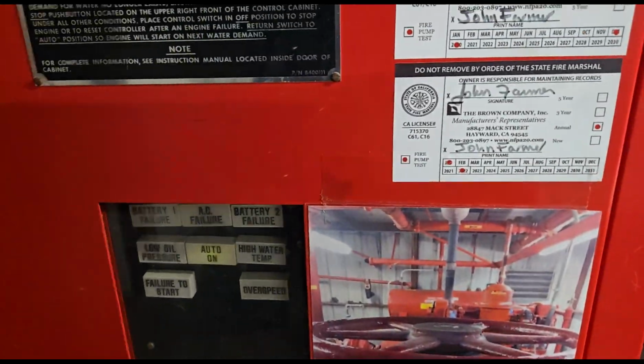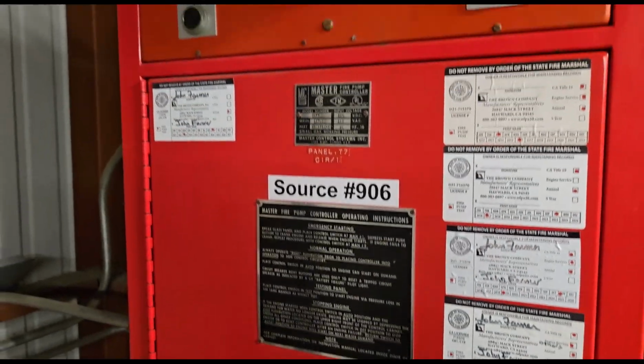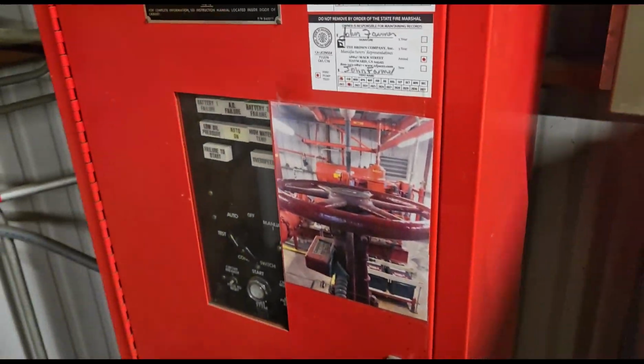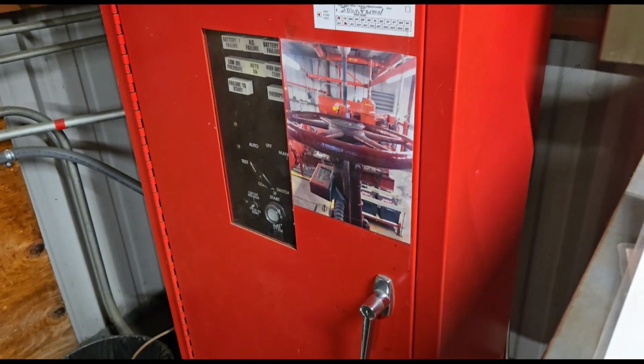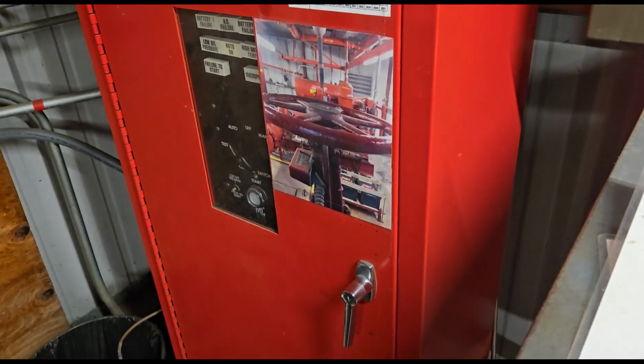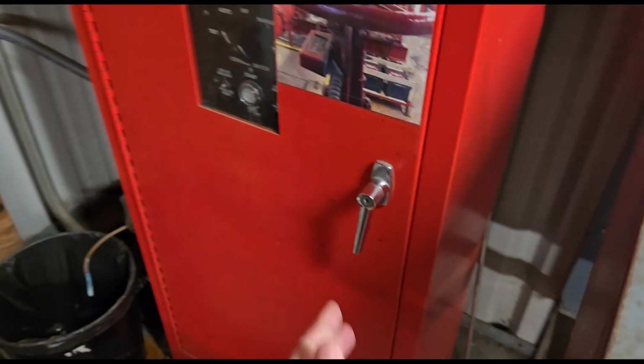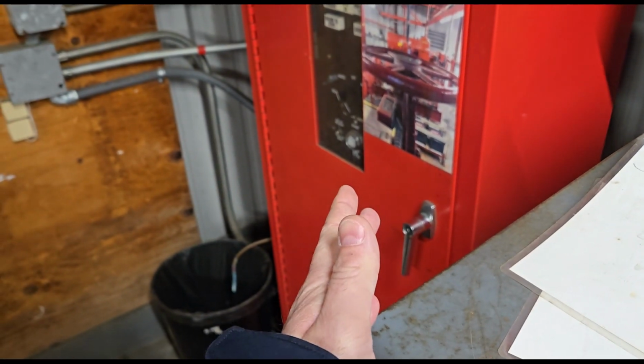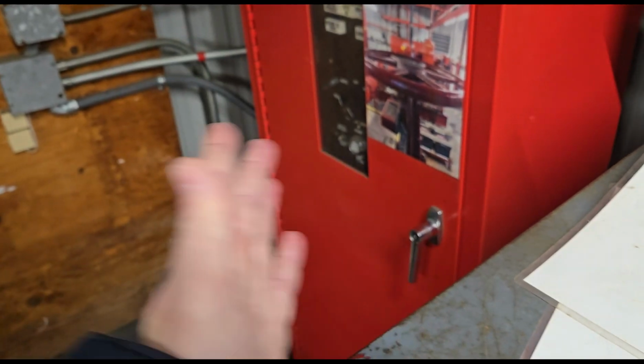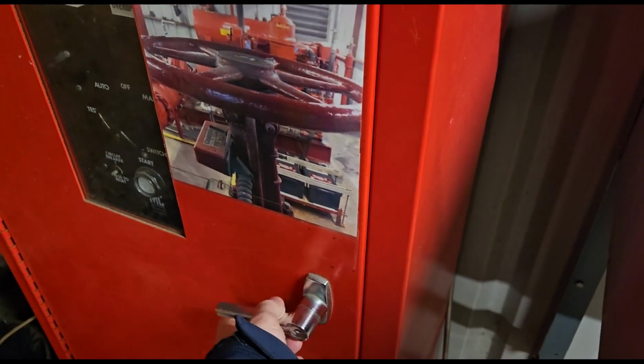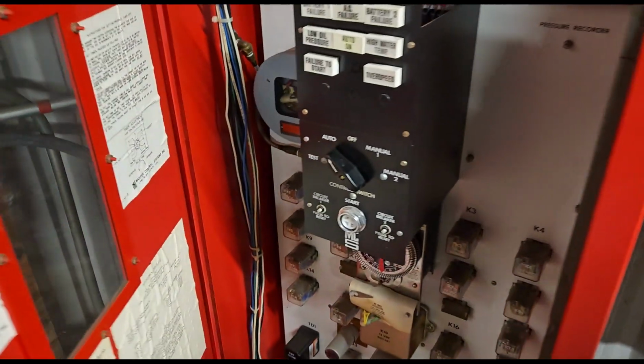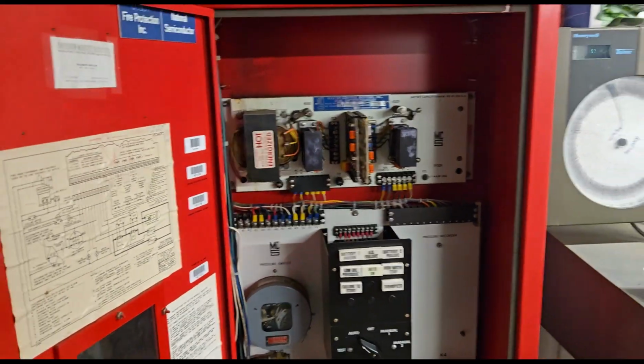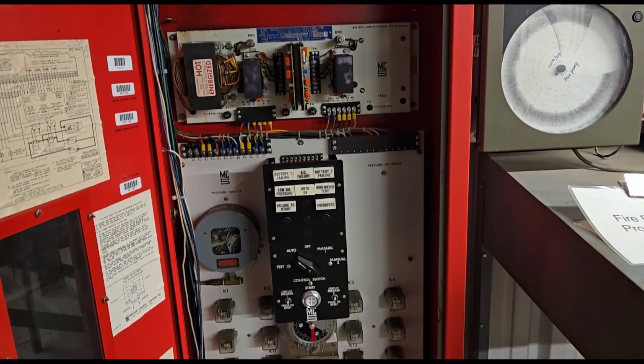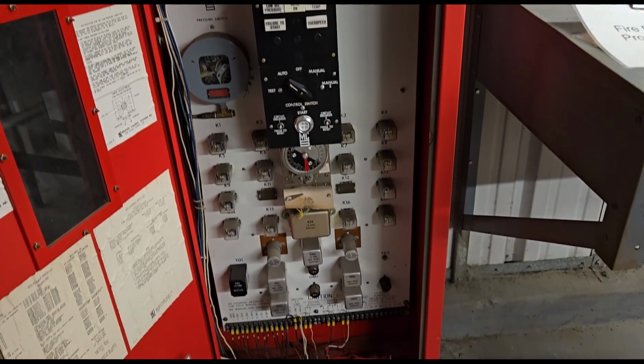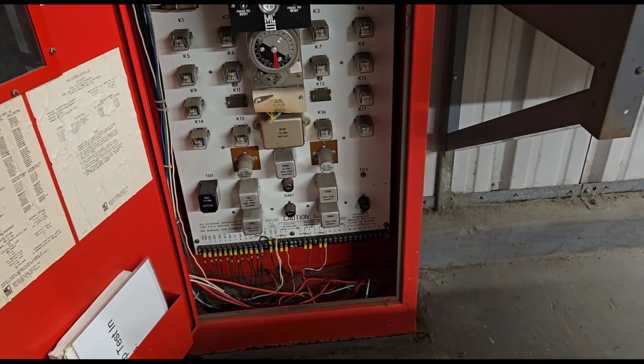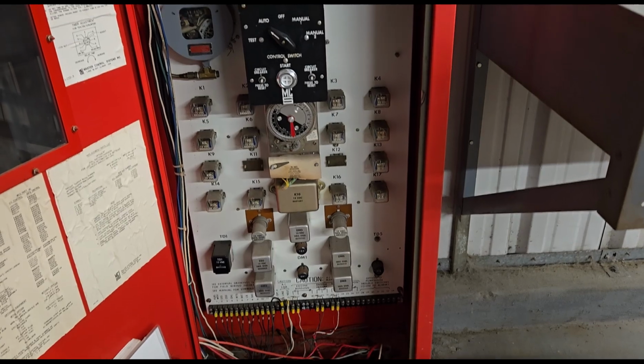Normally when operating a fire pump controller, you want to wear an arc flash suit. I do not have one, so I'm just going to take my own risk. So we're going to open up the panel. I'm just going to stand off to the side, that way if there is an arc flash or something, I'll at least be off to the side. So I'm just going to open the door. This is what the controller looks like on the inside. It's a much older controller for the diesel fire pump.